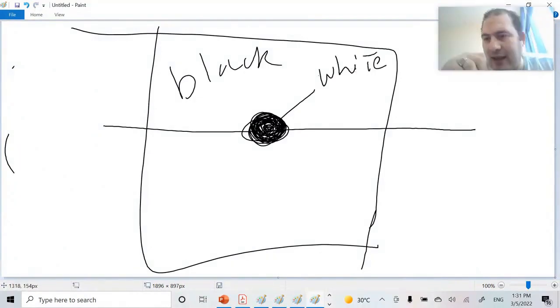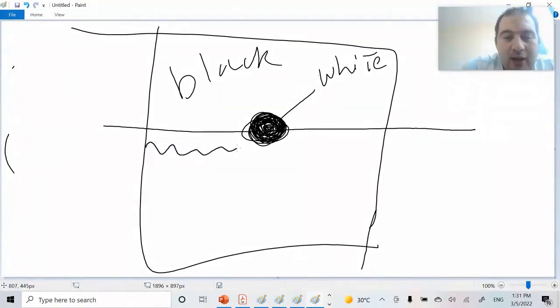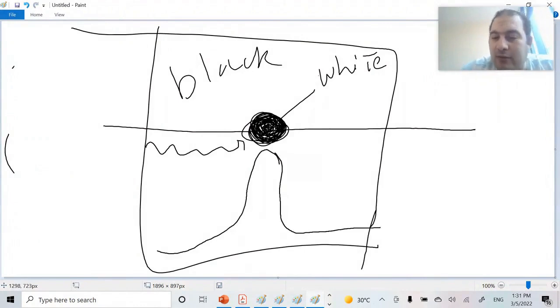I said I want to take a line profile. What is a line profile? It means I want to see the value of intensity at every point along the background. As it passes over my object, I found that this part I can call black, meaning it dropped a bit, until I reached the area of the object where the intensity started to rise, reaching the maximum at the center of the object, and then it dropped again, right? So this curve is called the line spread function.